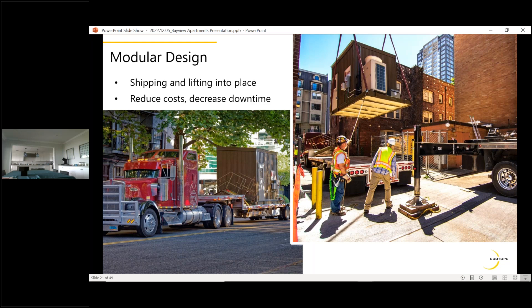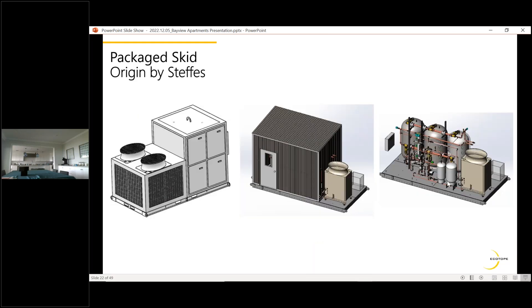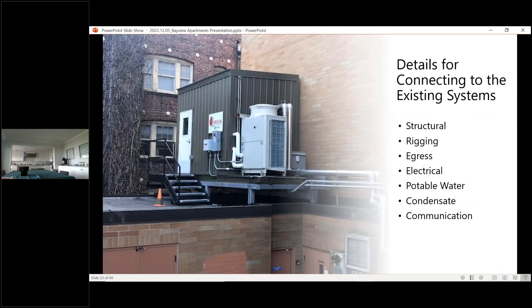Photos show the modular skid being delivered and lifted onto the roof. The right side shows what the current modular design looks like, while the left shows a conceptual future product version that Steffes has been developing. When working with this modular design, key engineering considerations include: structural requirements, rigging to get the system in place, egress, electrical requirements, and connections for potable water, condensate, and communications. This approach simplifies controls and piping design enormously by treating the whole assembly as a single piece of equipment.